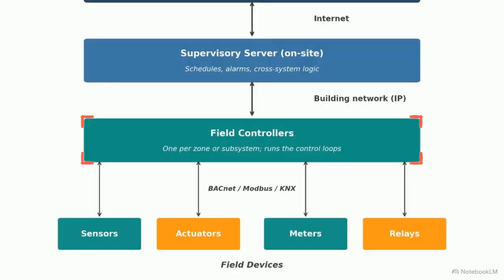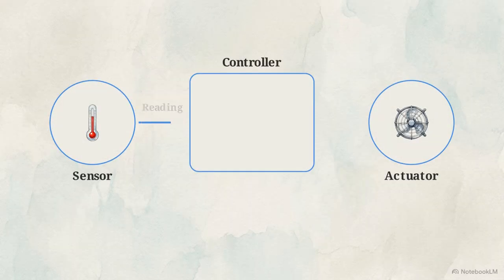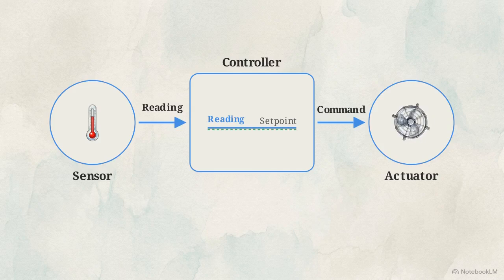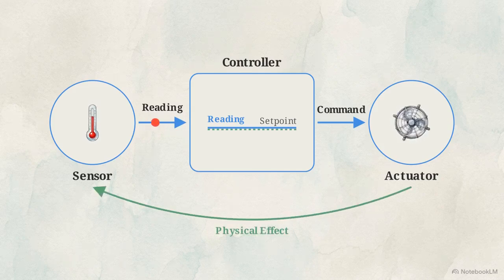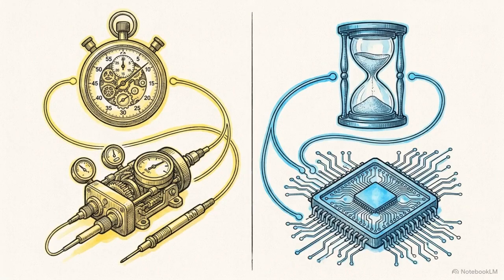Moving up one level, we find the field controllers. These are small, dedicated computers, typically installed one per physical zone or equipment subsystem. A field controller runs a continuous control loop. It compares the reading from a sensor against a configured target, known as a set point, and then commands an actuator to adjust physical outputs until the reading hits that target. While field devices detect changes in milliseconds, controllers process the control loop and issue commands in seconds.